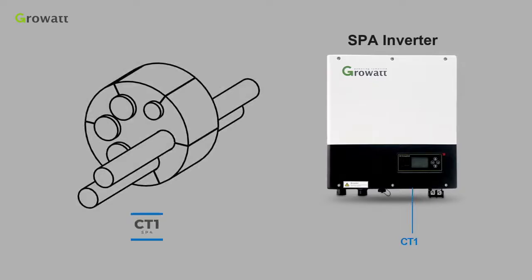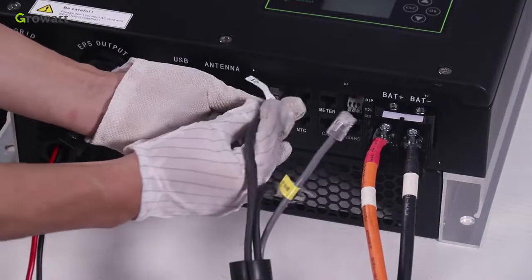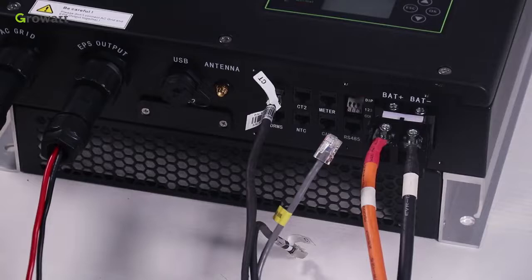Take CT1 for example. We need route the CT1 cable through an opening in the cable support sleeve. Thread the CT1 cable through the cable gland. Insert the RJ45 plug of the network cable into the CT1 pin connector on the inverter until it snaps into place.